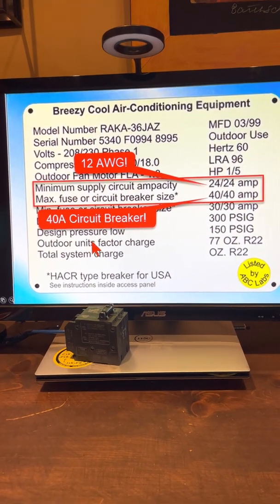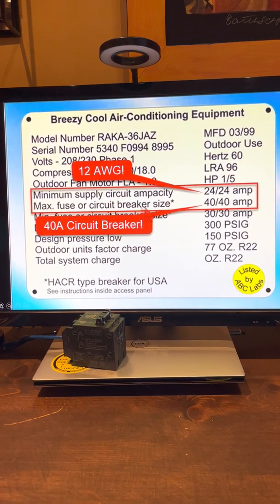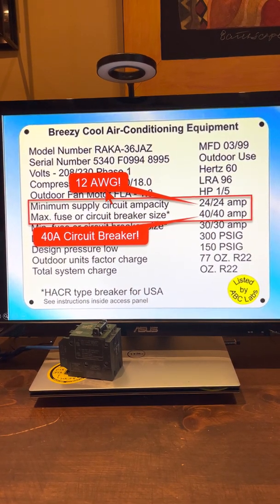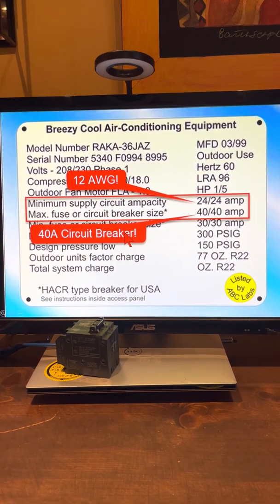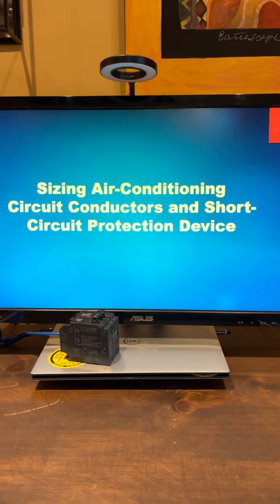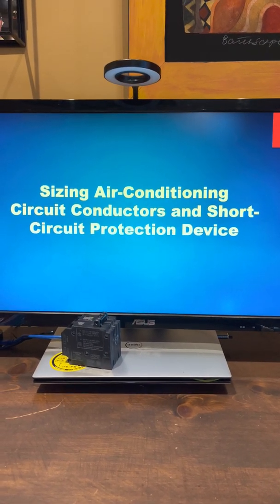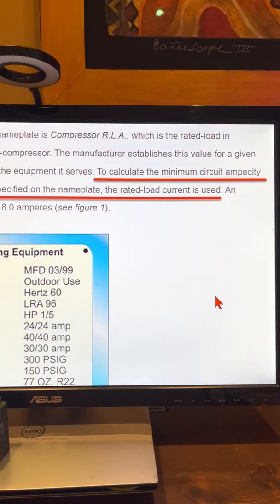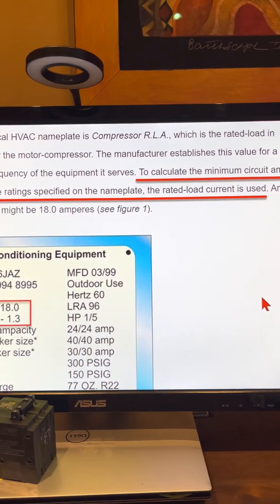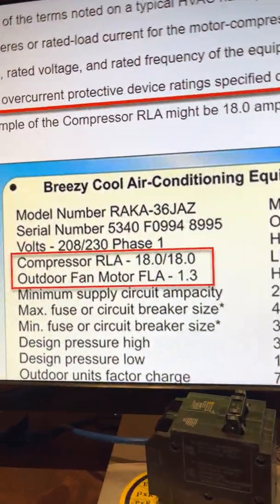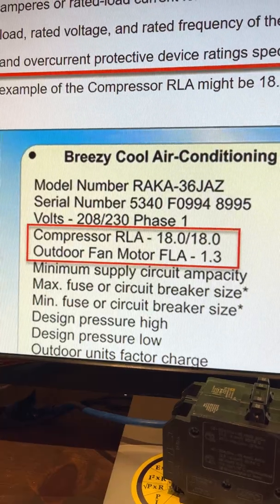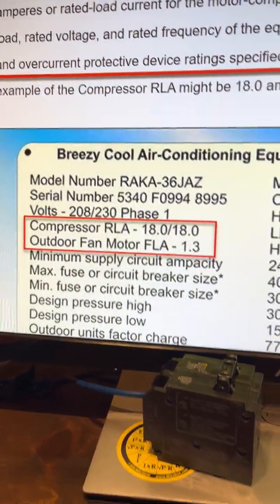What this article says is that if you take a look at the air conditioning nameplate and it says the minimum circuit supply is 24 amps and the maximum circuit breaker is 40 amps, then you can use a 12-gauge wire on a 40-amp breaker. Now, sizing air conditioning circuit conductors and short-circuit protection devices — to calculate the minimum circuit ampacity and overcurrent protection device settings on the nameplate, the rated load current is used. This nameplate has a running load amps of 18 amps for the condenser/compressor and 1.3 amps for the fan motor.